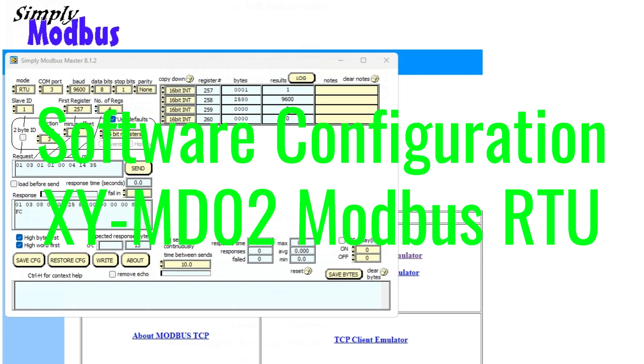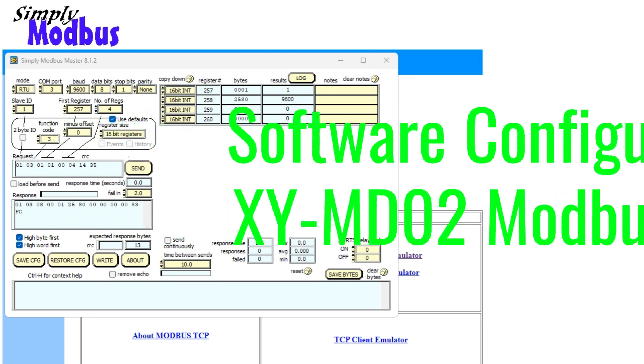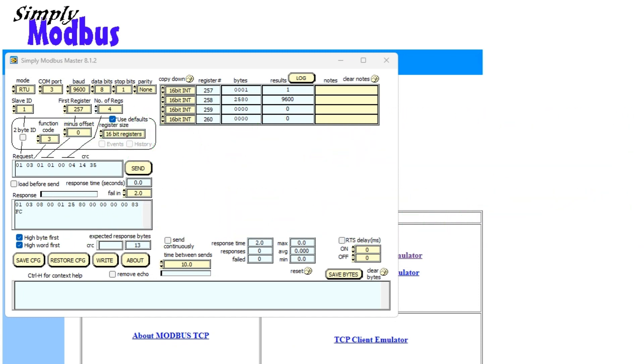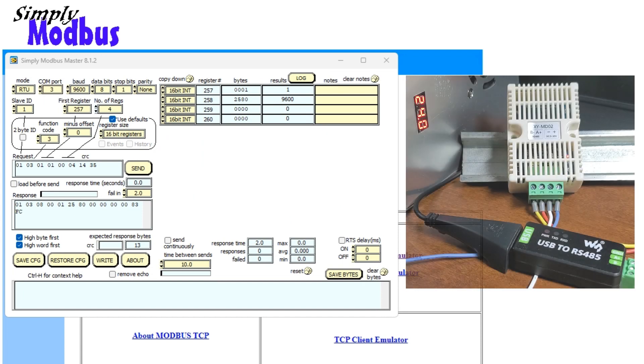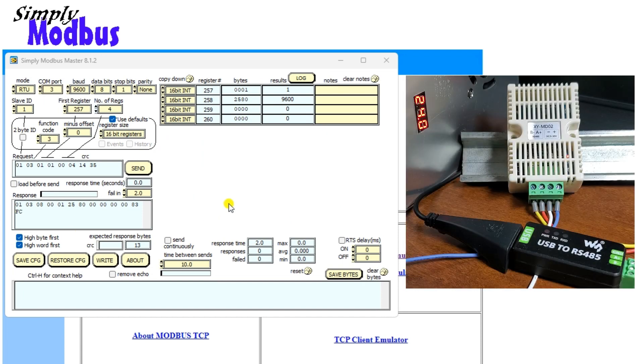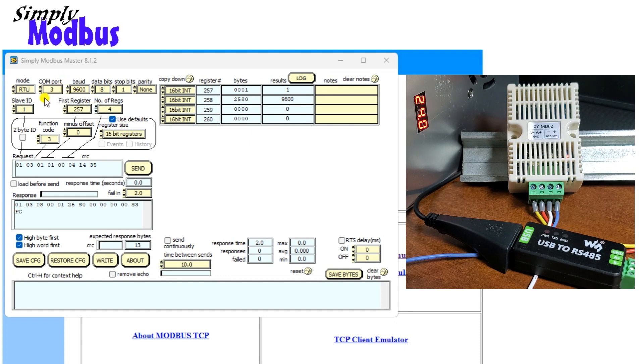Software configuration, XY-MD02 Modbus RTU. We will read the temperature and humidity to ensure that communication works as expected. The default parameters for the XY-MD02 sensor are unit address 1, 9600 baud, 8 data bits, 1 stop bit, and no parity.